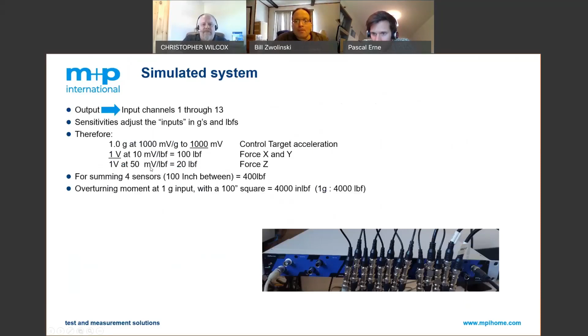There it is. Okay, this is the M+P vibration control run screen. I'm just going to start this up. This would be a calibration where you would bring it up and you would be checking that your forces look correct for the weight that you have. Force equals mass times acceleration. As you can see, I show some different forces.